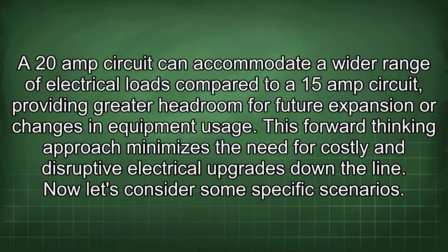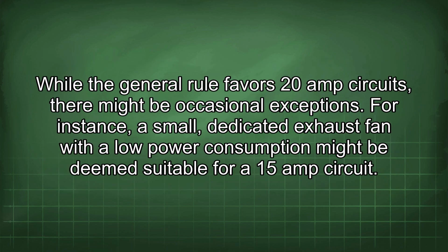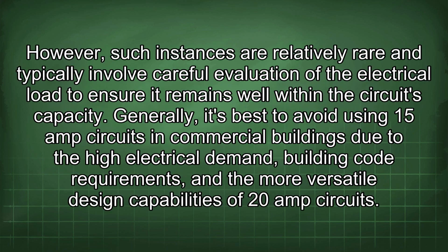Now let's consider some specific scenarios. While the general rule favors 20-amp circuits, there might be occasional exceptions. For instance, a small, dedicated exhaust fan with a low power consumption might be deemed suitable for a 15-amp circuit. However, such instances are relatively rare and typically involve careful evaluation of the electrical load to ensure it remains well within the circuit's capacity. Generally, it's best to avoid using 15-amp circuits in commercial buildings due to the high electrical demand, building code requirements, and the more versatile design capabilities of 20-amp circuits.